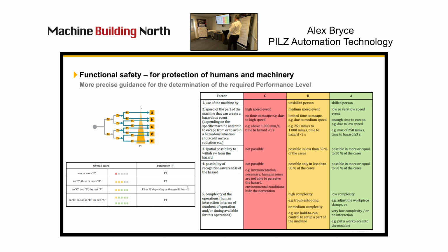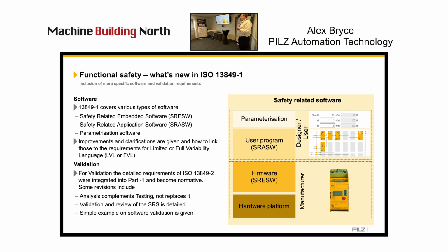There's also a requirement, since software is now considered a safety component, that talks about the two different types of software. You might have a programmable safety relay or similar, and there are requirements for safety related embedded software - the firmware that controls the device - and safety related application software, the bit you write to say, if I press an e-stop do that, if I open a guard do this, or whatever it might be.